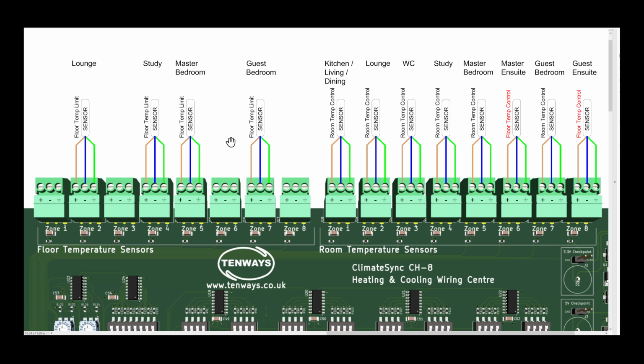So to avoid it stopping too early, we would normally put the sensors just under the floor but away from the floor heating source. So for example, if you have water pipes in the floor, don't put the sensor near the pipes, put it a bit away from there. Now we will look at the room temperature sensors. A sensor on the wall in the room, the best height for it will be 1.4 meters. That's the advised height for it.